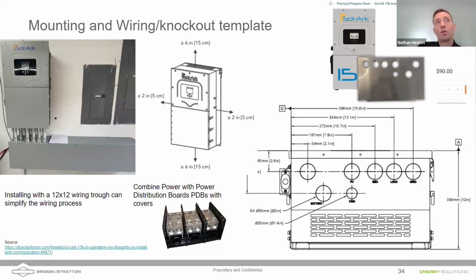So if you're going from solar directly to loads, that's where you can get that 98% efficiency on the inverter. You're not using it to run the charging equipment inside the inverter to charge the batteries, right? So it kind of depends on output. If it's going from solar to batteries to loads, you lose a few more percent. If you're using AC coupled solar, you lose an additional maybe 10%. So I think that's the best I can do with that question because I'm not better informed on the topic.